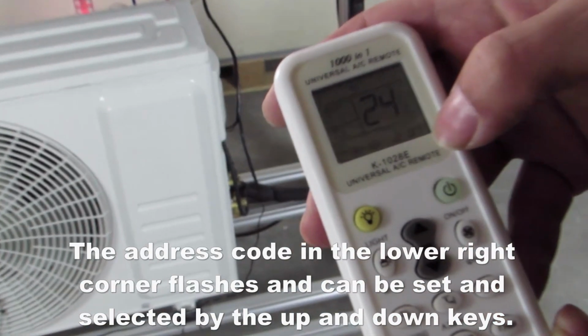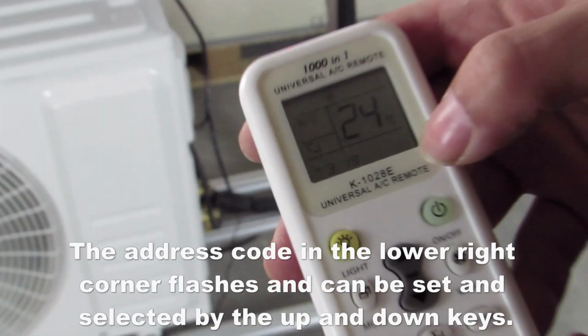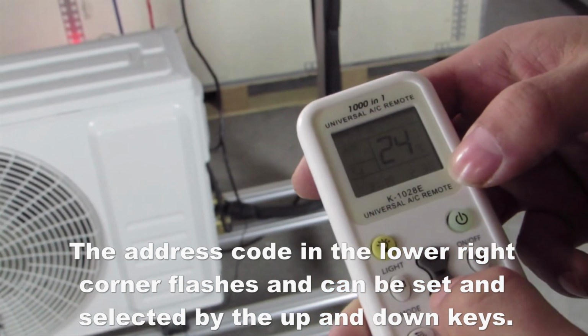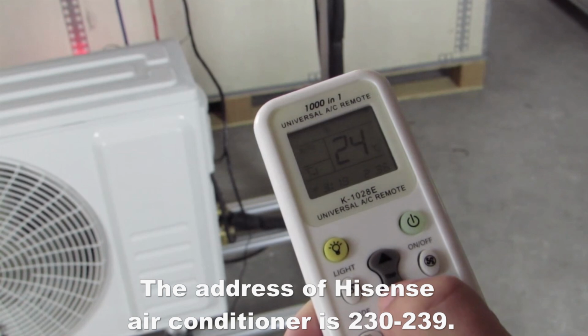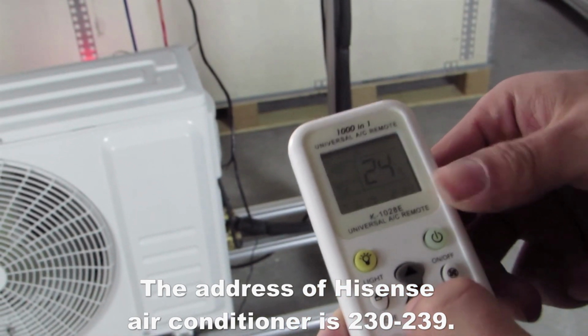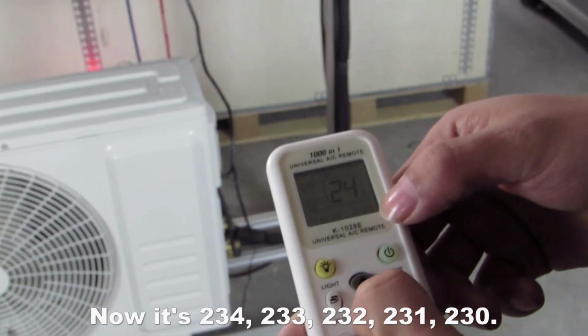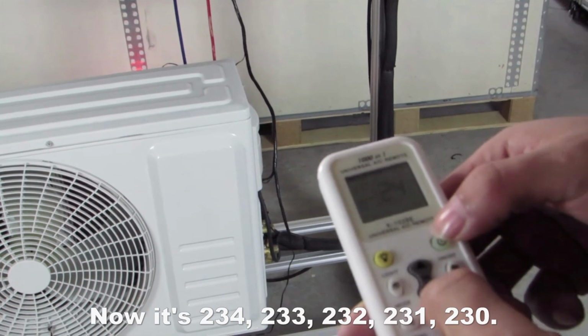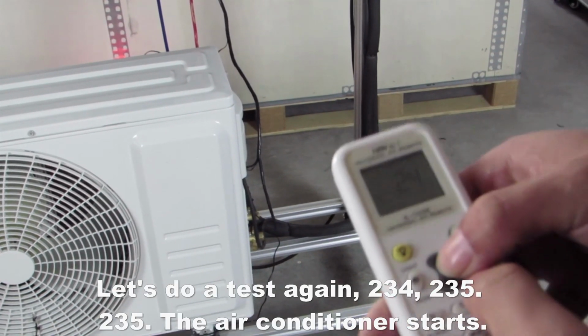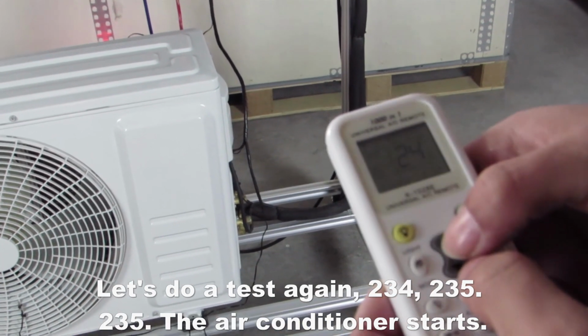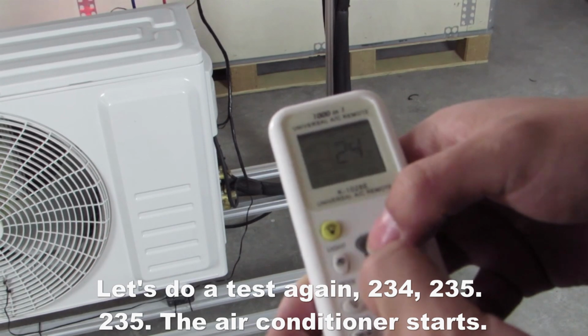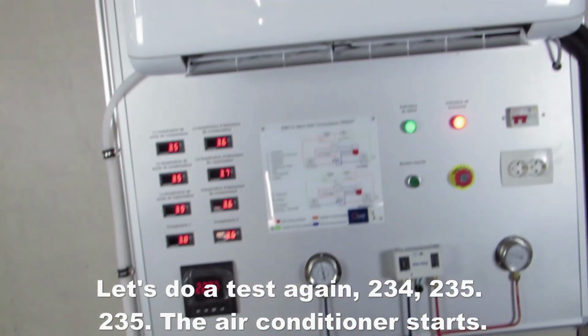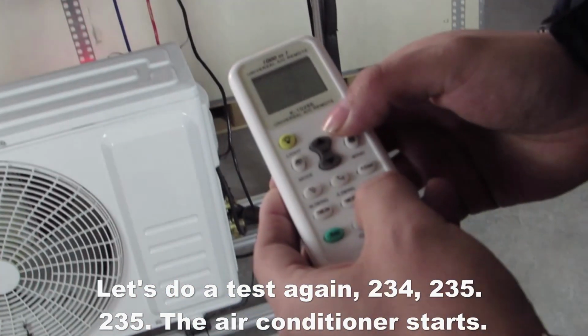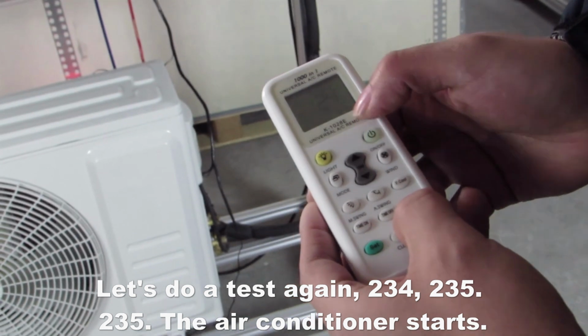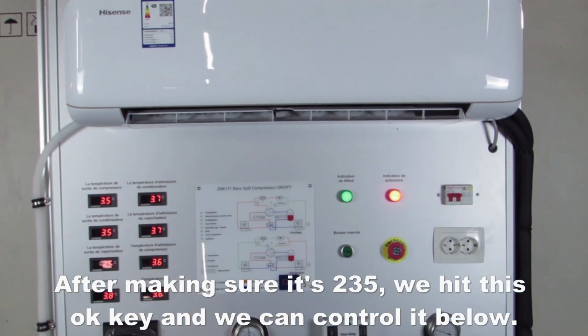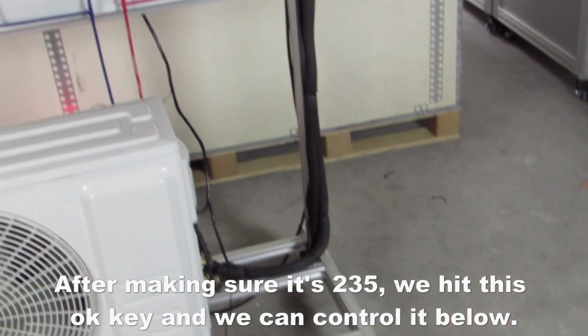The address code in the lower right corner flashes and can be set and selected by the up and down keys. The addresses of Hisense air conditioner are 230 to 239. Now it's 234, 233, 232, 231, 230. Let's do a test again. 234, 235. The air conditioner starts. After making sure it's 235, we hit this OK key and we can control it below.